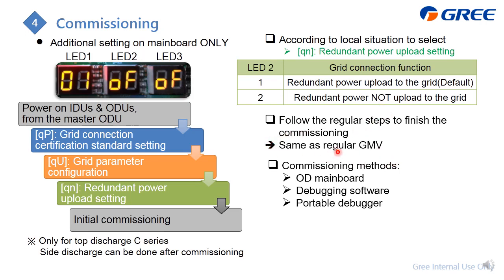As for the commissioning methods, it's the same. You can do it on three ways: from the outdoor unit PCB, from the debugging software on your PC, and with the portable debugger. But the setting of these three parameters can only be done on the outdoor unit PCB.